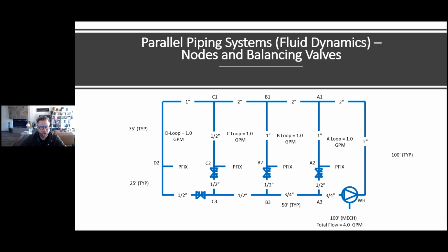So if you find that you have too large of a temperature drop through your system and you have to, let's say, increase the flow rate starting from 1 GPM, let's say you have to start bumping up the flow rate at some of the loops based on the balancing valve, you may need to increase your hot water return pipe size some, so that way you're not causing erosion corrosion depending on your pipe material. So if you do that though, remember our equations for heat loss, you're going to have an additional heat loss on your hot water return side. Now, some people will ask the question, well, Christoph, do I have to account for the hot water return temperature loss? Or aren't we only worried about supply?